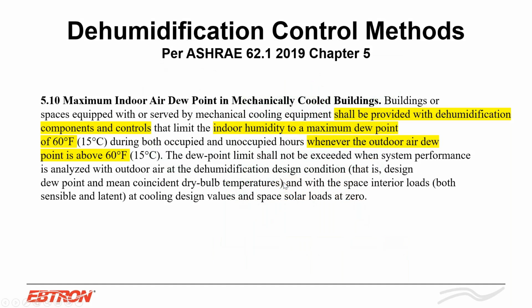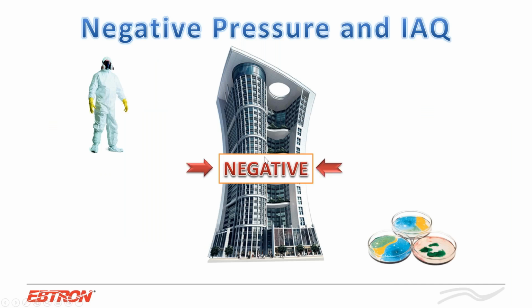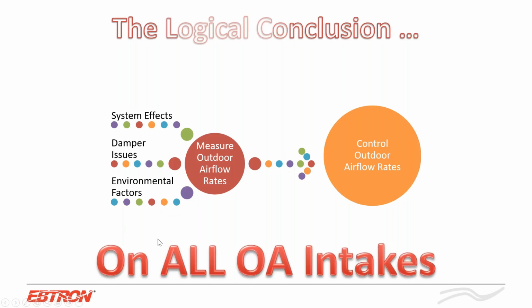Well, ASHRAE says under Standard 62, under Systems and Equipment, Section 5.10, that anytime the outside air dew point temperature is above 60 degrees F, you have to be providing controls to dehumidify the space. And why are they saying this? Because of the potential for mold, of potential for fungal growth, if you're having humidity control issues and temperature control issues in your space. So what you want to do in terms of building pressurization is put a flow meter on your supply, return, and outside air and be able to control your flow rates.